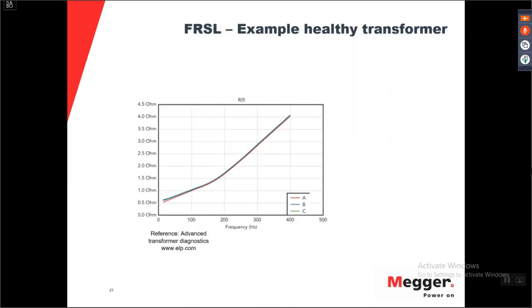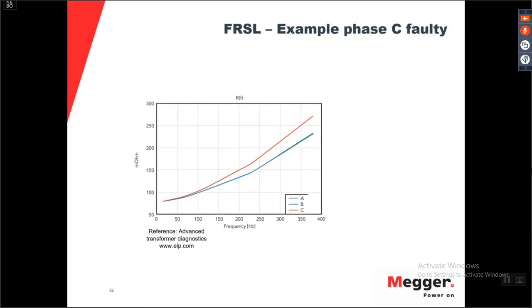Now what you will do is you will make this short circuit impedance test at multiple frequencies for all three phases. So here you can see phase A, phase B, and phase C plotted from 1 Hertz up to 400 or 500 Hertz. Of course, it's the same type of winding, so they should behave very similar, and all three phases look the same. But if you have a short circuit between the parallel strands giving rise to the higher eddy current losses, a typical faulty curve would look like this. So then two phases look the same, and then one has an increased loss for the higher frequencies.